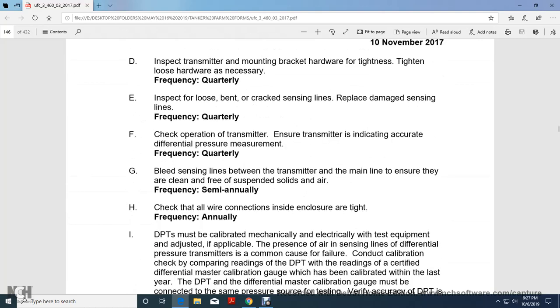Frequency: quarterly. Inspect the transmitter mounting bracket hardware for tightness, and tighten any loose hardware if necessary. Quarterly, inspect for loose, bent, or cracked sensing lines, and replace damaged sensing lines. Quarterly, check the operation of the transmitter. Ensure the transmitter indicates accurate differential pressure measurement. Quarterly, bleed the sensing lines between the transmitter and the main lines.